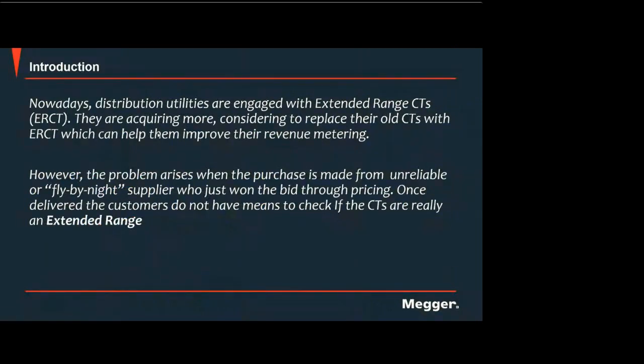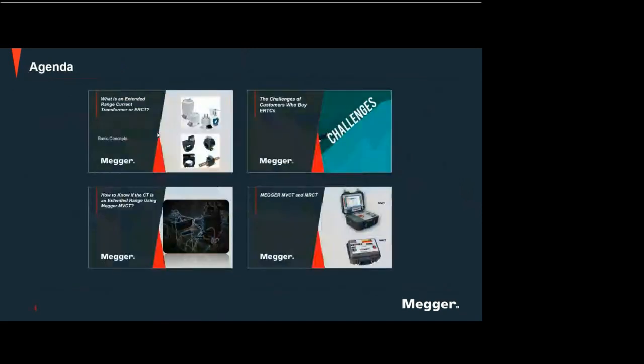As you may know, distribution utilities or electric co-ops in the Philippines, or maybe in any part of the world, are engaged with extended range CTs. They are buying more. This is to consider replacing their old CTs with the ERCT, which they believe can help them improve their revenue metering. However, the problem arises when the purchase is made from an unreliable or fly-by-night supplier who just won the bid through pricing. Once the CTs are delivered, they don't have the means to check if the CTs delivered are really extended range. Okay, so this is what the problem is.